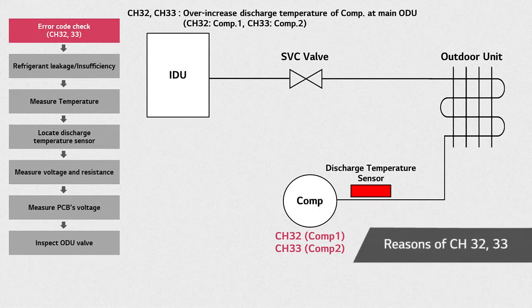These are CH32 and CH33 errors. These errors are caused by excessive discharge temperature of compressors 1 and 2 respectively, so their solutions are quite similar.